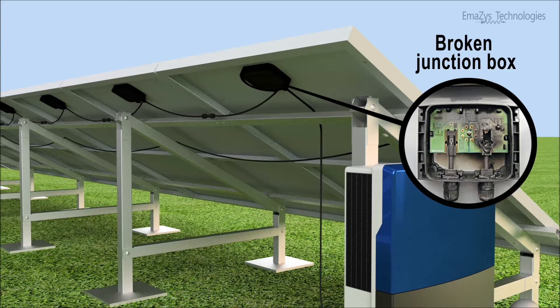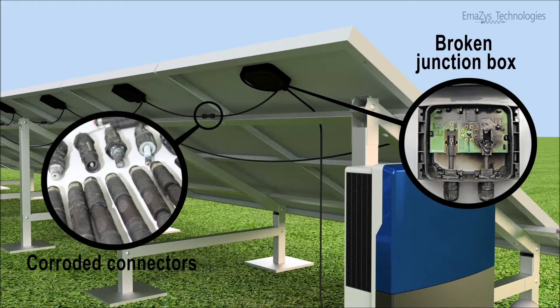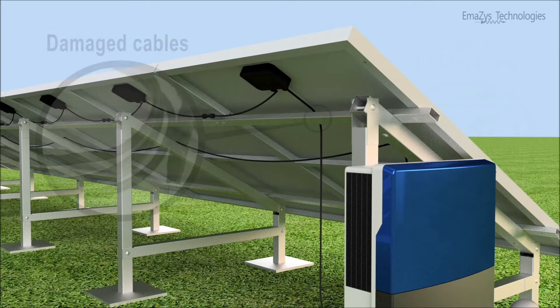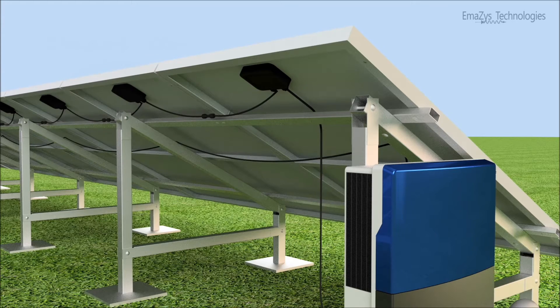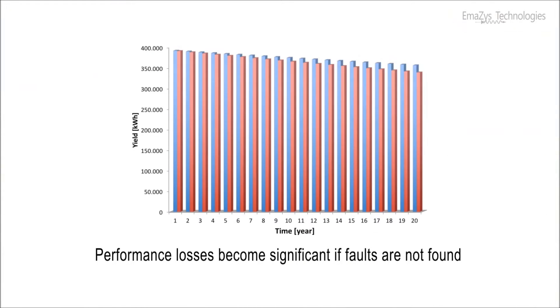Bypass diodes must also be functional. Corroded connectors, which frequently lead to series resistance issues and subsequent losses. Damaged cables and other insulation problems, which cause grounding faults that lead to energy loss from full strings. Performance losses become significant if faults are not found, and over time this means lost revenue.